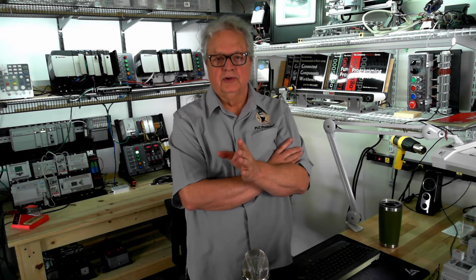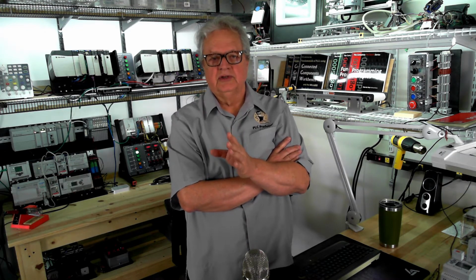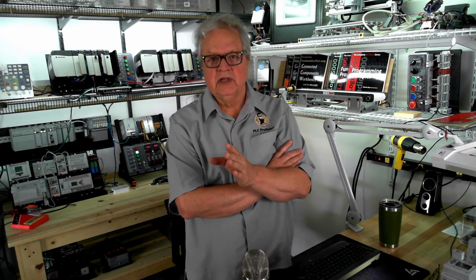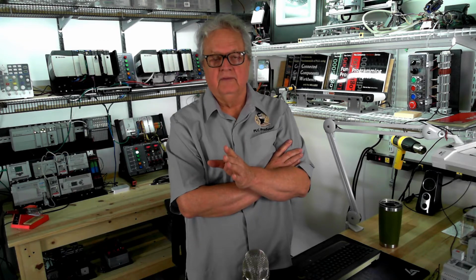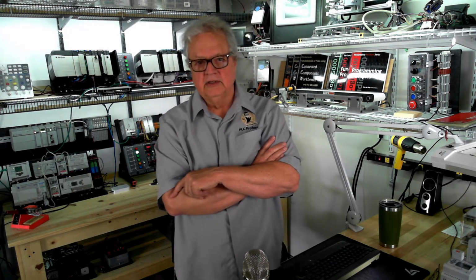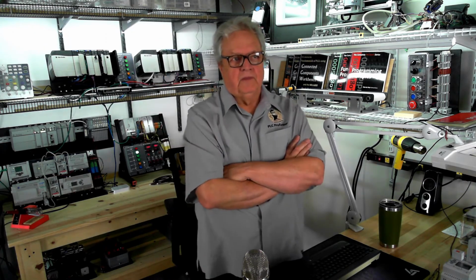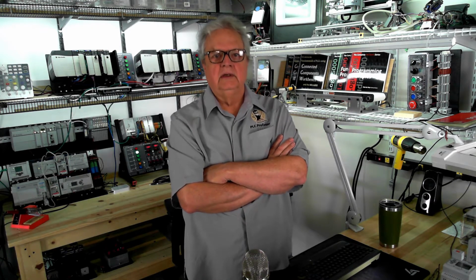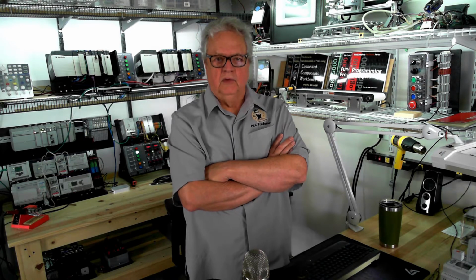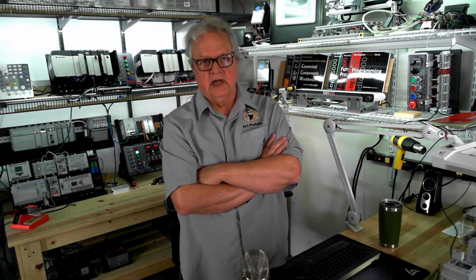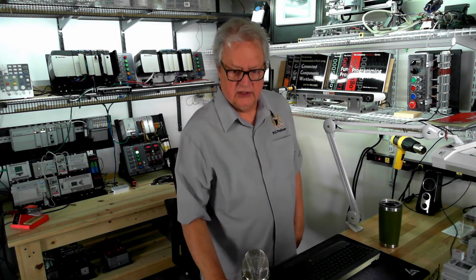So when the rung goes true, a rising edge coil will set that bit that it addresses in memory on that scan. The very next scan, it's going to set it right back off because it's a one-shot. So the Micro 800 does give you a few more instructions to accomplish what you want to accomplish in detecting and controlling instantaneous events, one-scan events. So let's get into this. This will take more than one session, but let's get into the first session and get on with it.